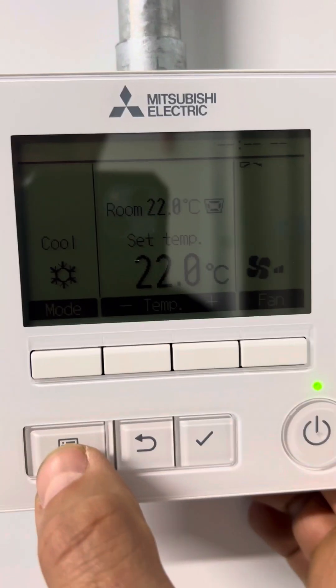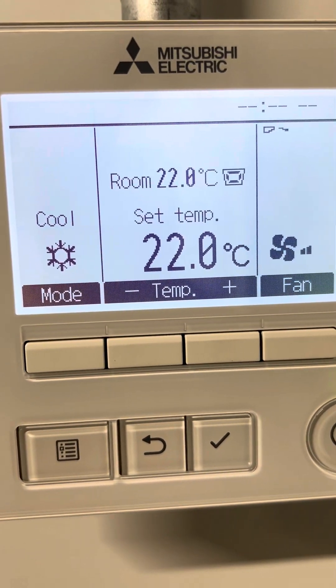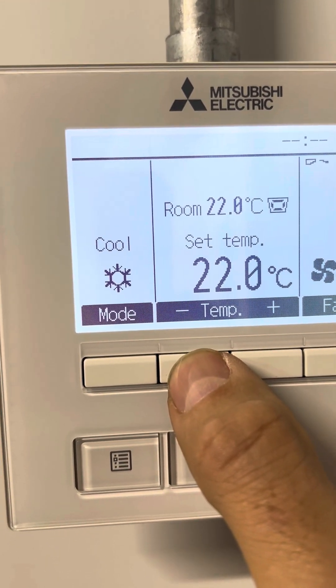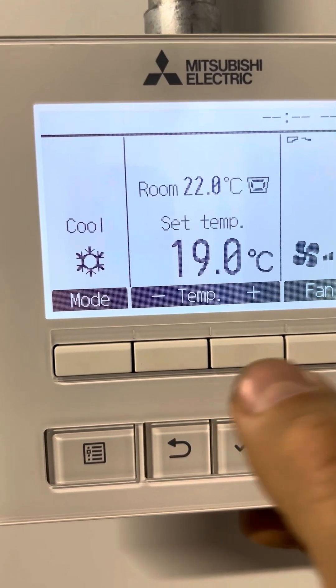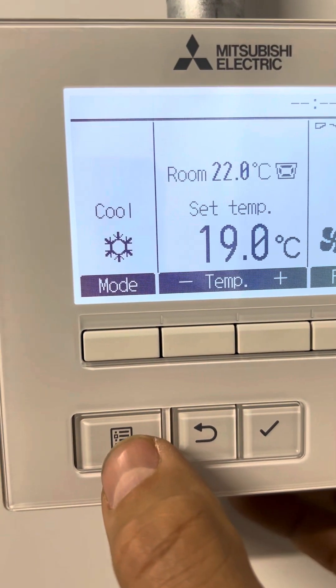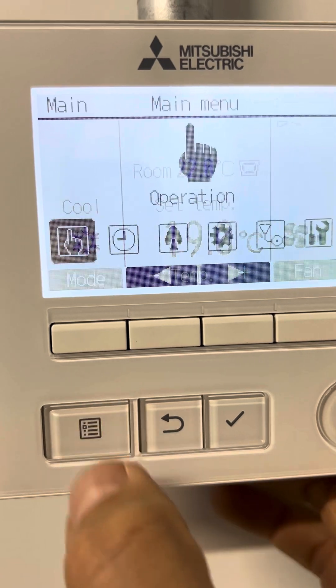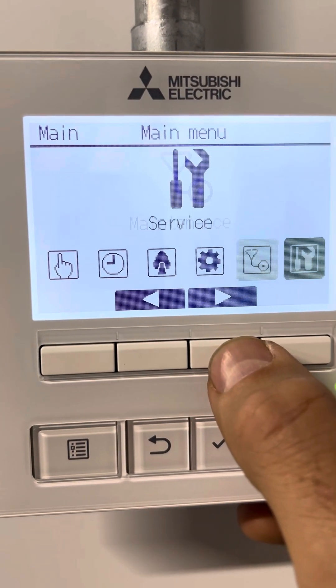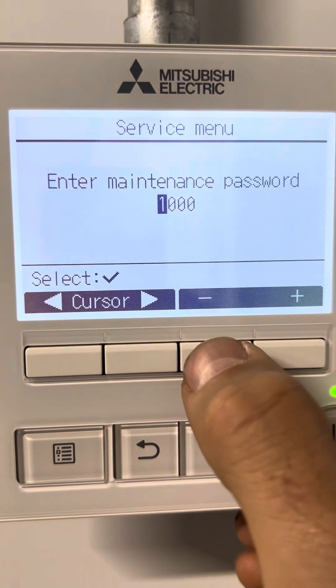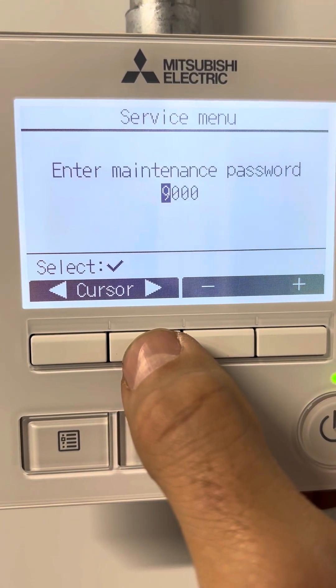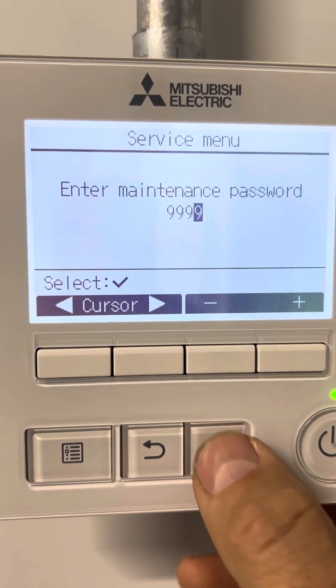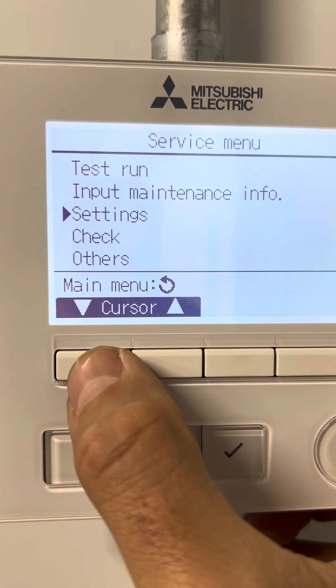By using different request codes. To do that, first I will drop the set point so that the unit will run. To get the request code menu, we go to Service. The default password on these controllers is 9999. Then we go to Check.